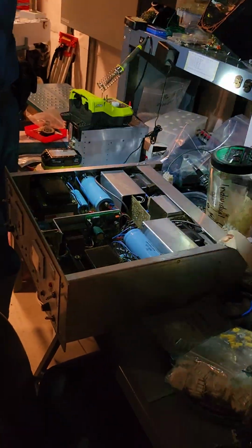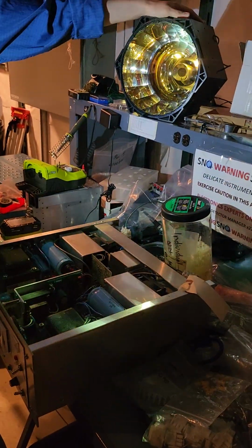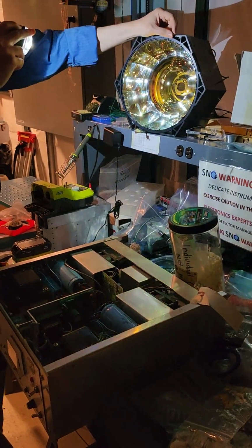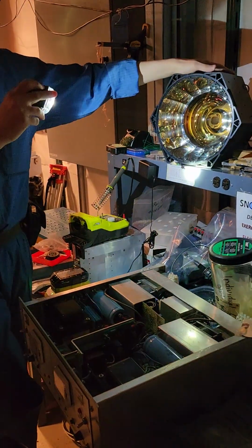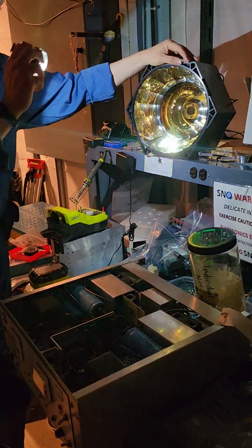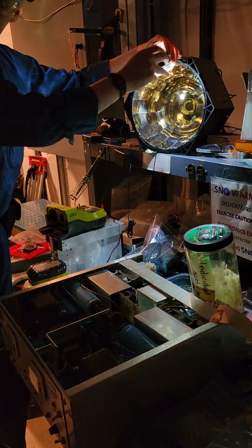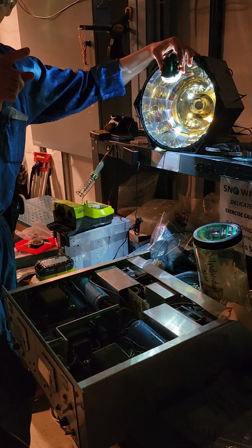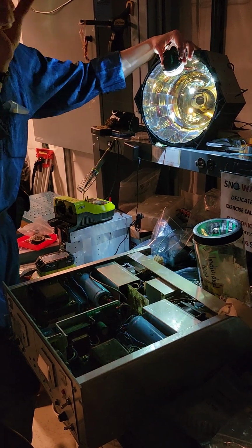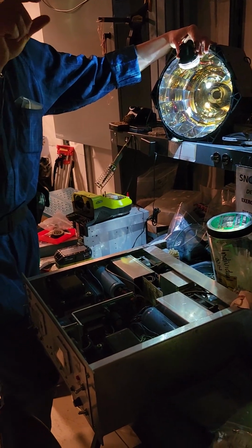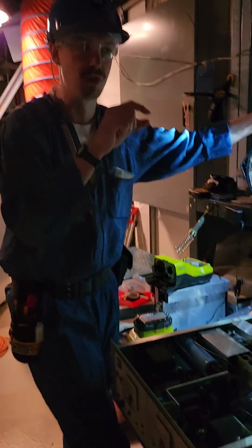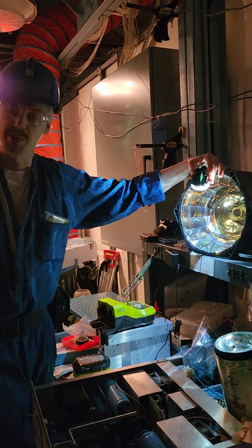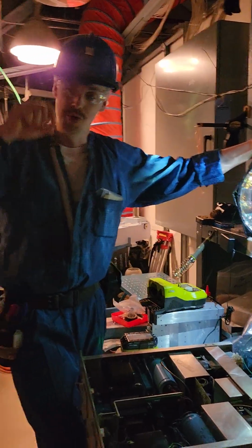When a photon comes in and hits the photocathode, these utilize a process called the photoelectric effect, where a photon deposits onto the photocathode and releases a photoelectron. The energy of that photoelectron is proportional to the energy of the photon coming in, so you can get an idea of charge just looking at that electron. But one electron is never good enough to look at as a signal, so we need to amplify it. This is where the multiplier part of photomultiplier comes from.